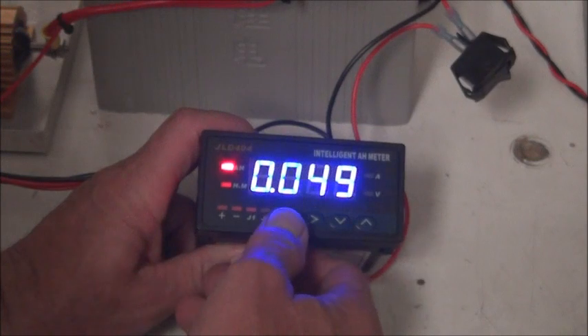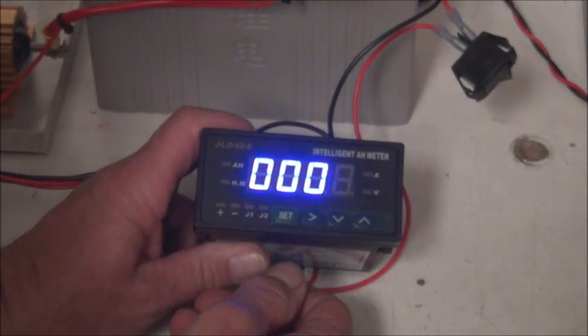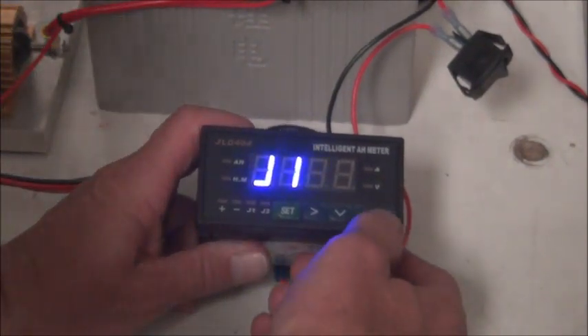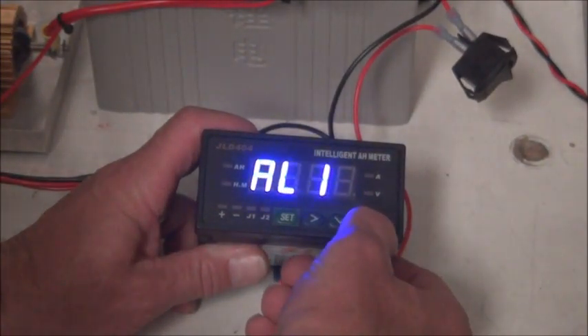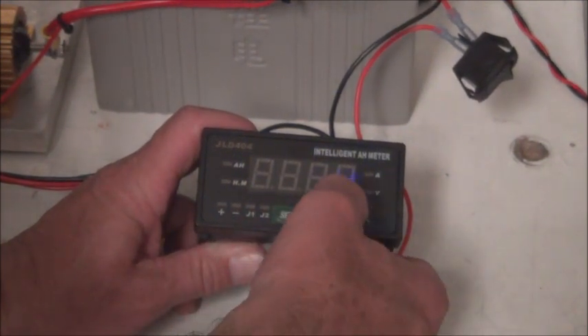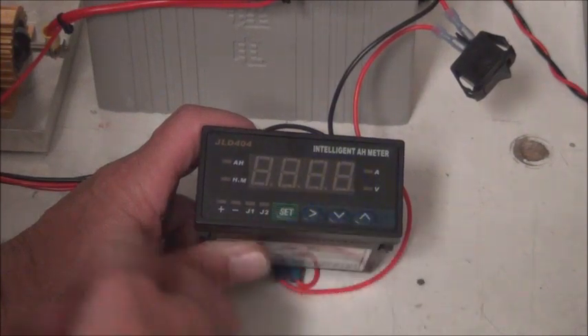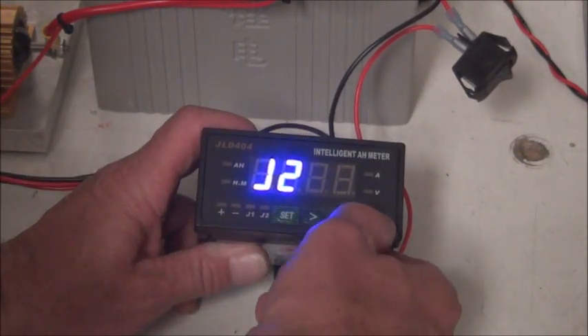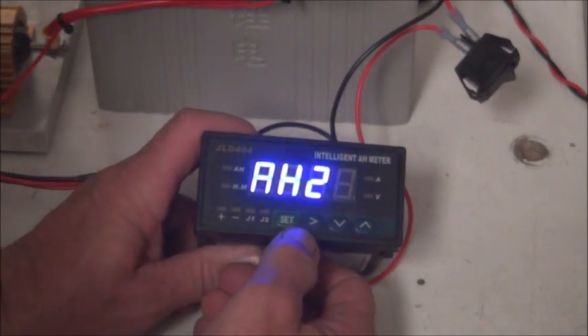Now to set up the relay, we're going to enter 0, 0, 0, 1. And that takes us to the relays. We have it set up on J2. So I'm going to skip through all the J1 related ones. On J2, we're using volts. You can use amp hours, amps, or volts. We, of course, we're using volts.